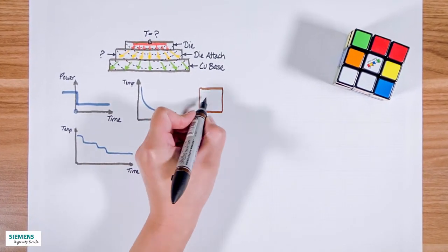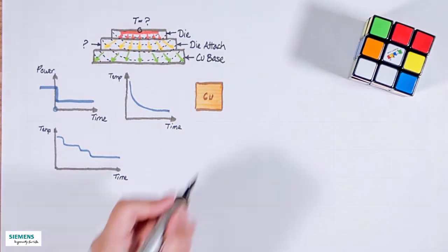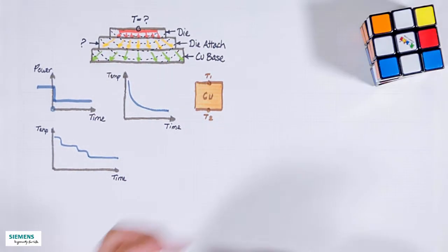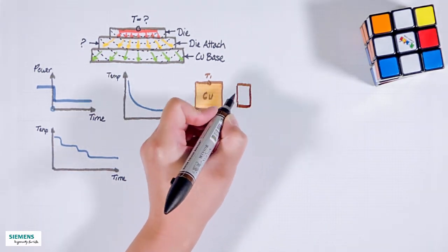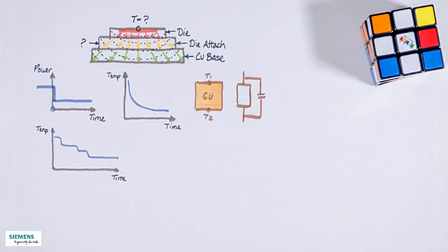If we have a simple structure, for example, just a block of uniform copper, how can we describe it? The heat comes from the top. We can describe it with a thermal resistance and a parallel connected thermal capacitance. The thermal resistance will make sure that if we heat it up from this point, the temperature will be different here.